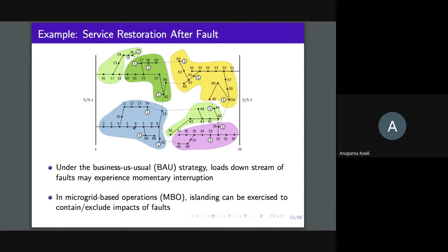Then what would happen, Matthew? Once this isolation is done, what would happen? Then we can energize again from other parts. So once you turn on the circuit breaker here, the parts of circuit I'm highlighting right now, nodes 2, 3, 4, 10, 11, 12, 13, 14, all of them can get energized again up to node 5. But nodes 7, 8, 9, 68, 69 are going to continue to remain offline because 5-6 has been isolated, so this link is no longer functional. Everybody see this? Everybody with me?